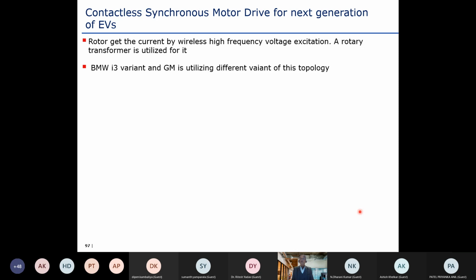What we are doing is using a conventional synchronous motor and removing the slip rings and brushes from the rotor circuit. Instead, we connect an inductive link: a high frequency inductive link voltage receiver and rectifier unit in the rotor. This high frequency inductive link is fed supply from the stator side through a different inverter.